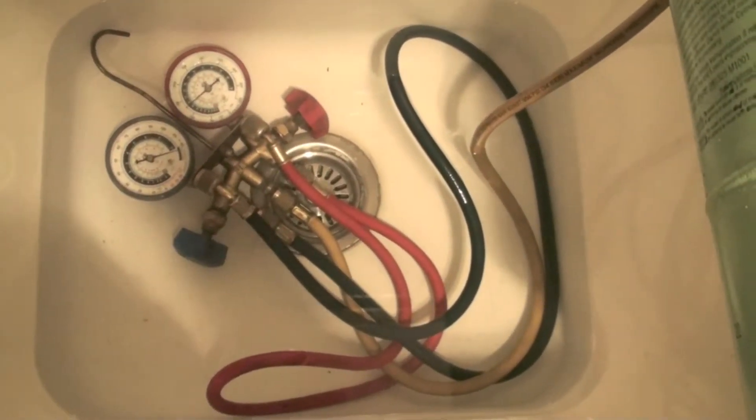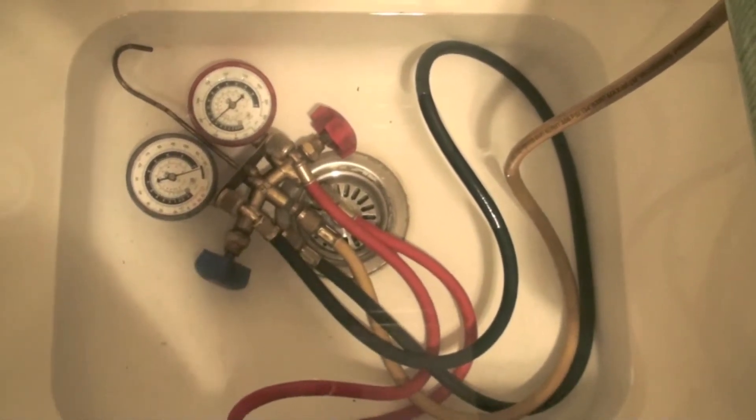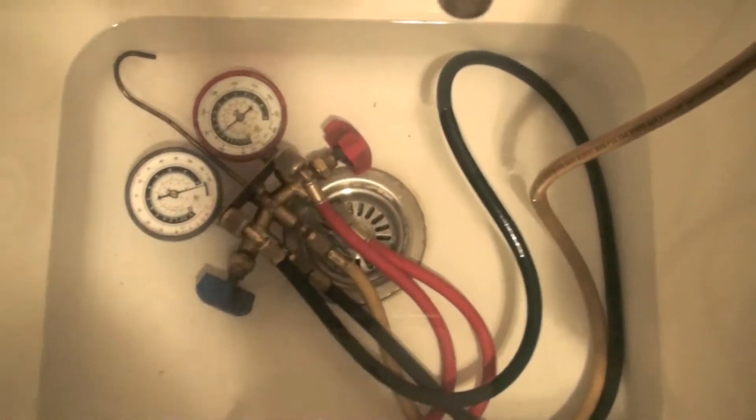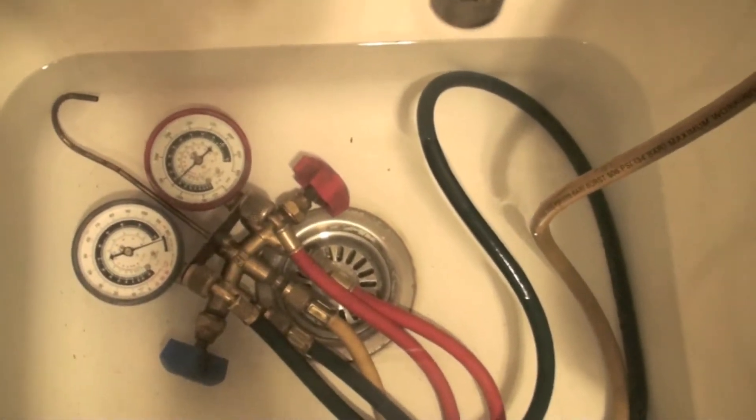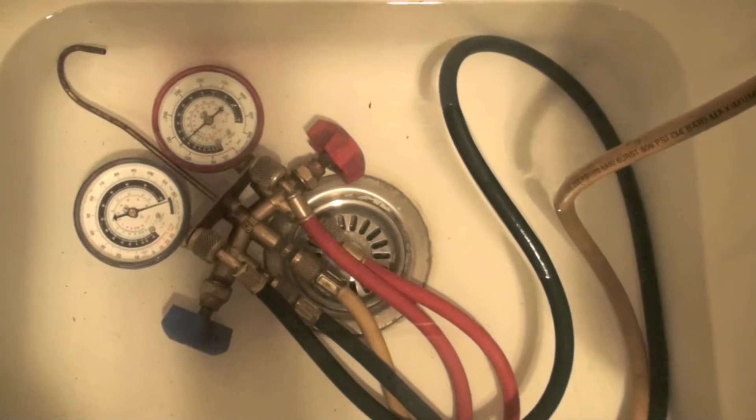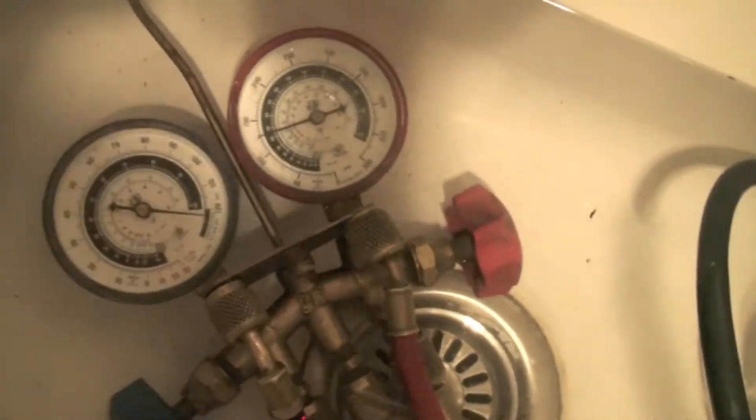You might wonder why I have immersed my gauge set in water. This is something I do usually at the beginning of the cooling season to see if there's any leaks. Now I'm going to get a little closer.